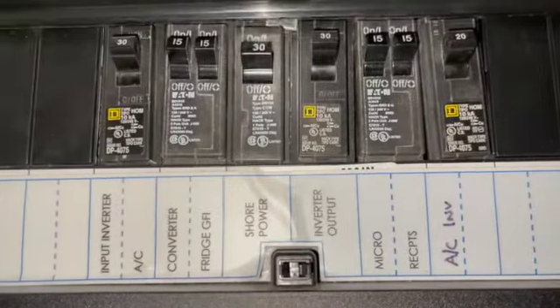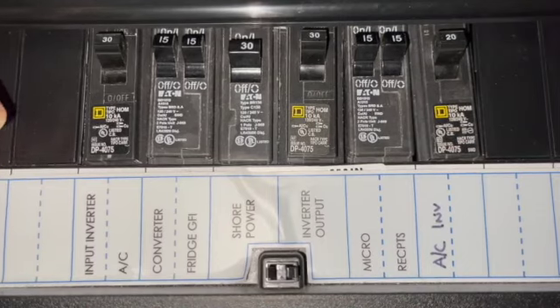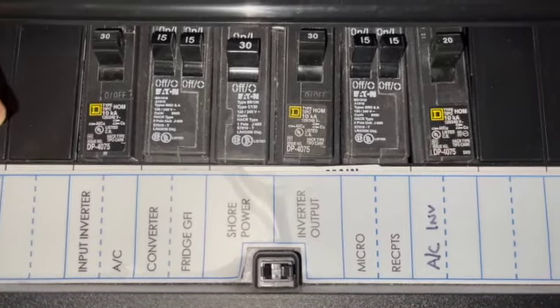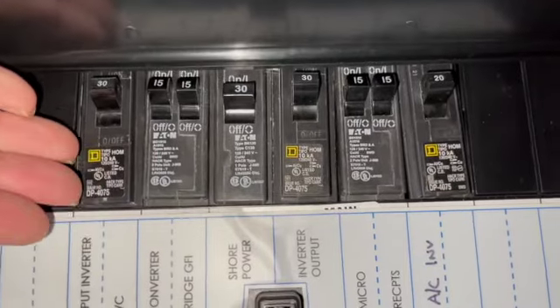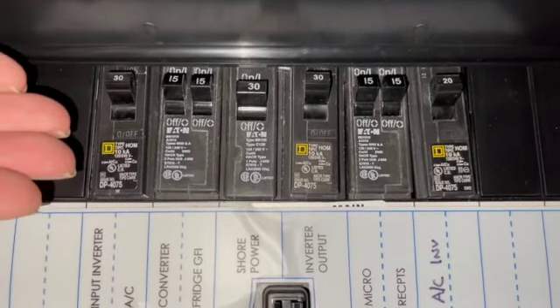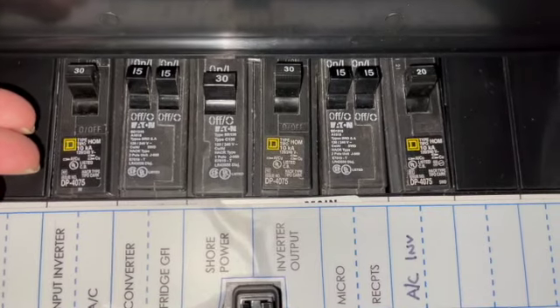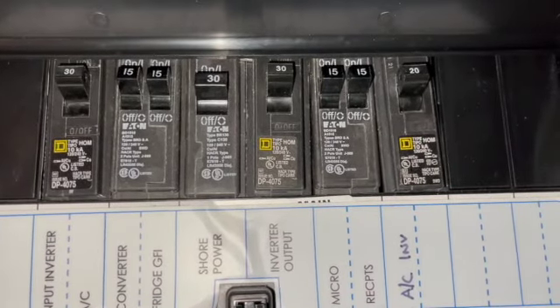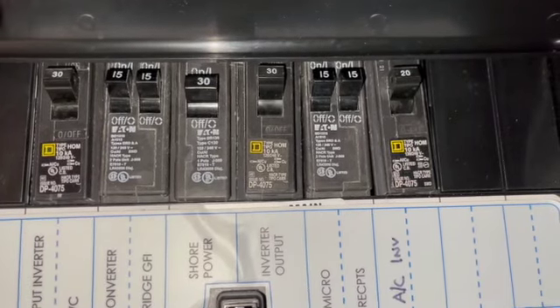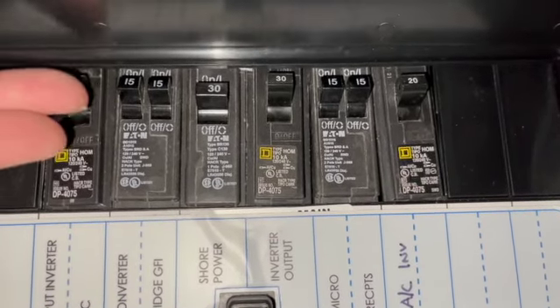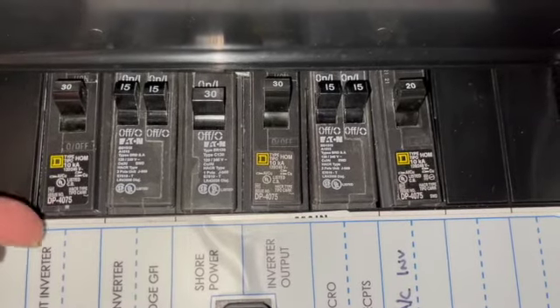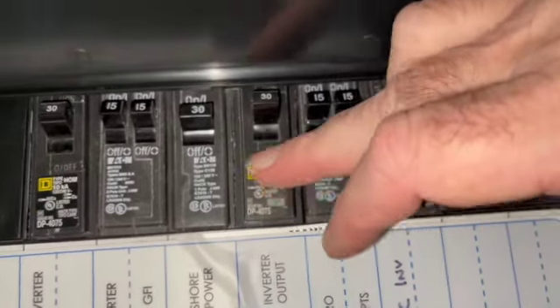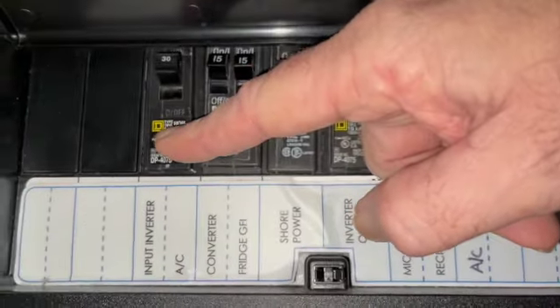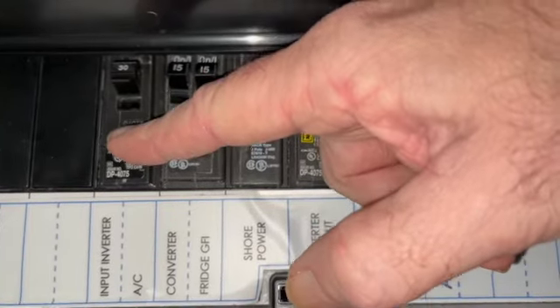So this is something I probably should have done right up front when I first installed the 3000 watt inverter. As you recall, I've upgraded the wiring to the system to 10 gauge wire that's suitable for a 30 amp circuit. So the 3000 watt inverter is really a 30 amp service, but I had left the 20 amp breakers in here for both the input to the inverter and the inverter output. So what I just did recently is I took this, which used to be a double breaker, one for the input to the inverter and one for the air conditioner.